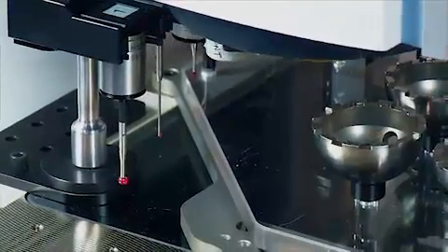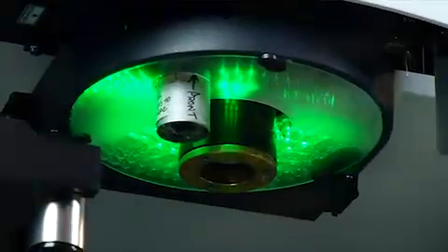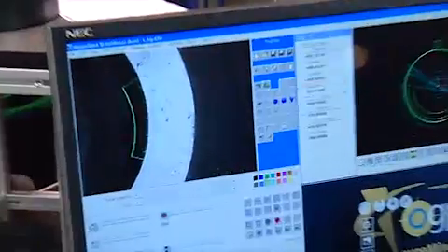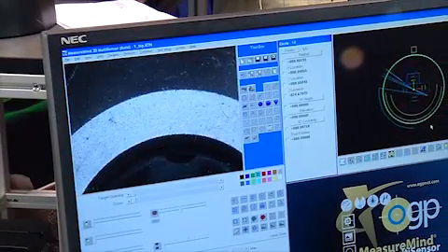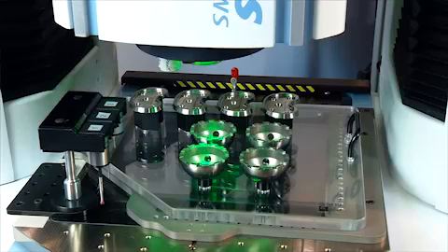Docking the probe now. Putting the probe away so that it has room to use laser and video. Here it's using video to make multiple video measurements. The video tool is good for measuring change in contrast, so where surfaces meet, which are defined by geometries that are lines, circles, arcs, and curves.